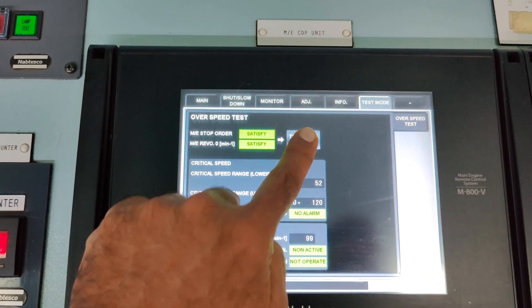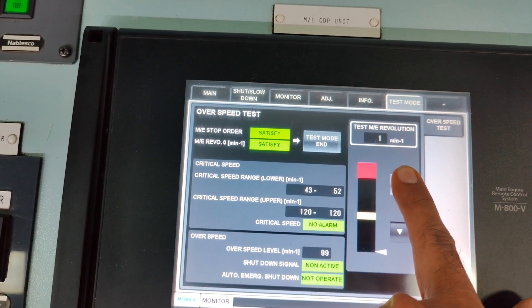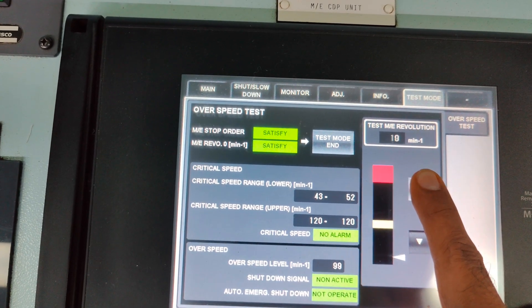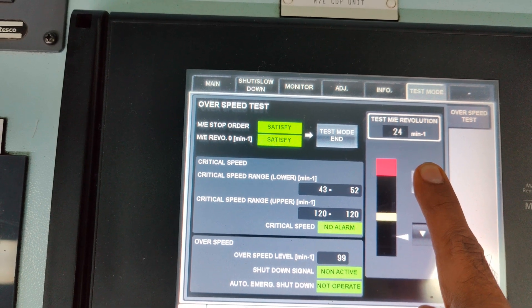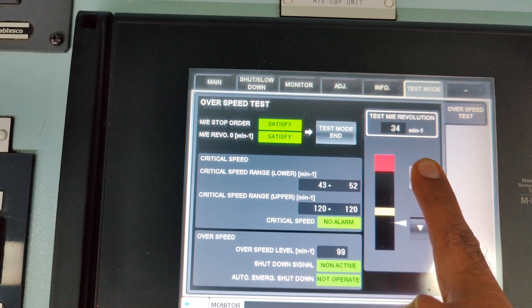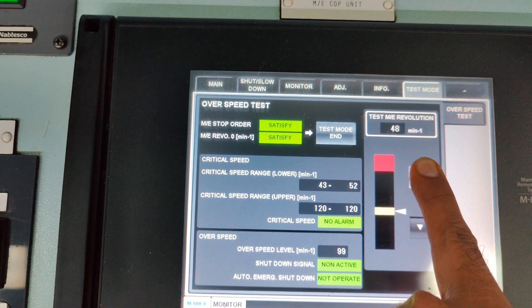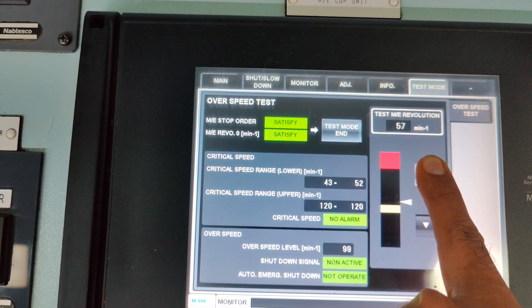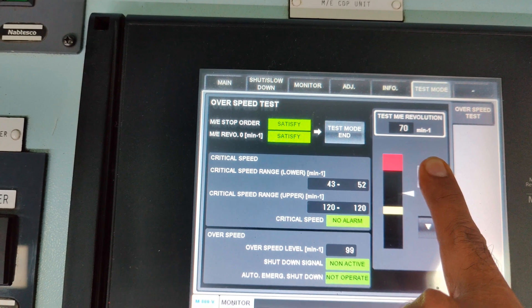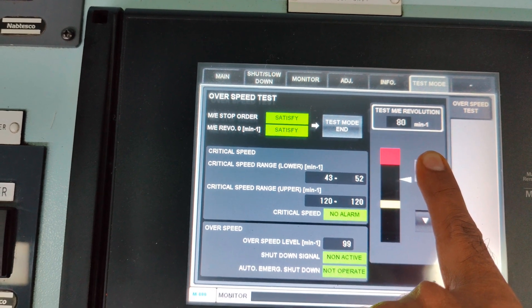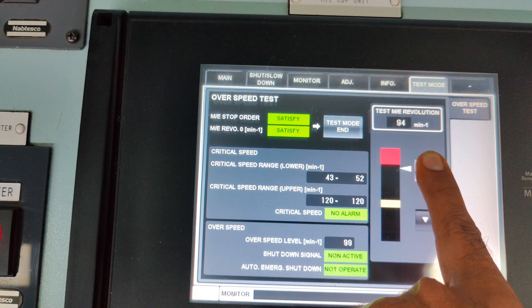Now to simulate the overspeed alarm, select the test mode start and raise the main engine revolutions above 99 RPM. As the remote control system is in test mode, we can externally generate a signal for increase in the main engine RPM. The same signal is forwarded to the control systems to generate an overspeed alarm and activate the auto slowdown safety systems of the main engines.